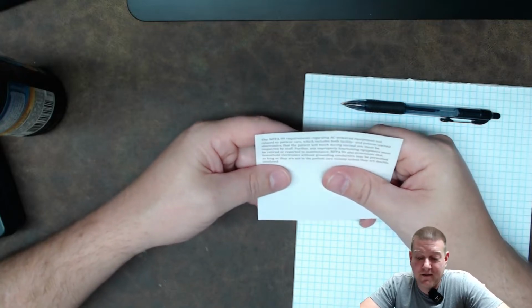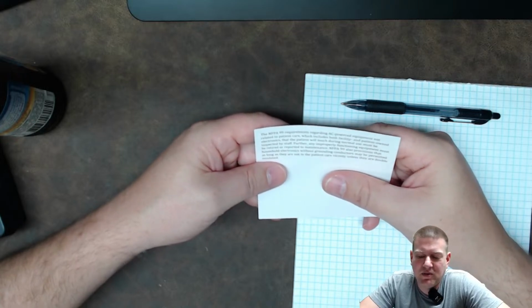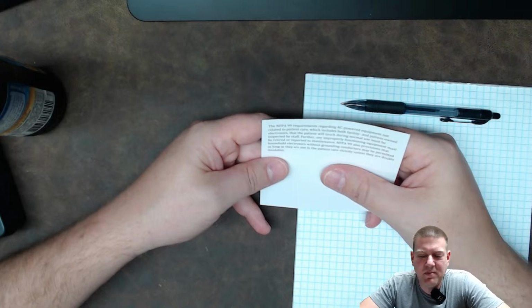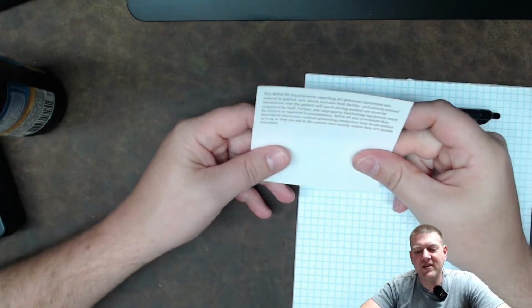So medical staff can inspect them to see if they're safe. Further, any improperly functioning equipment must be retired or reported to maintenance. NFPA 99 also provisions that household electronics without grounding conductors may be permitted as long as they're not in the patient care vicinity and as long as they're double insulated. Bam.